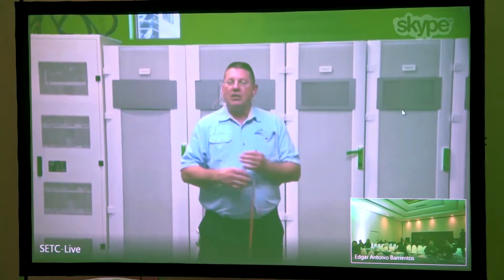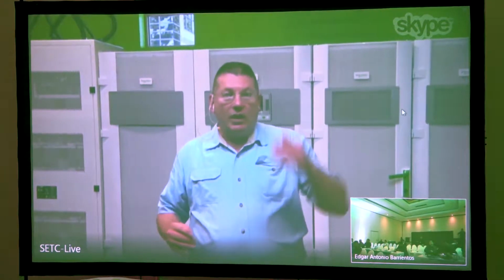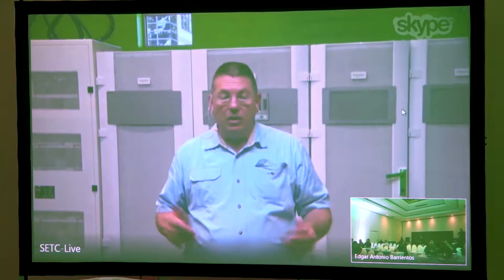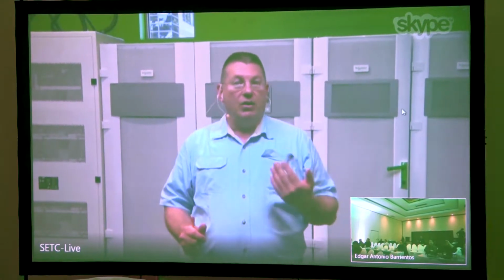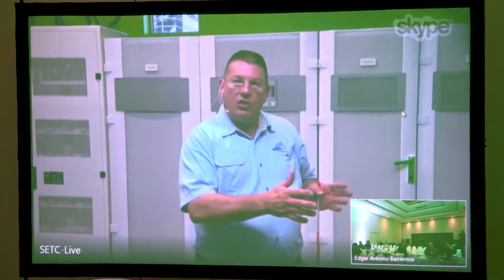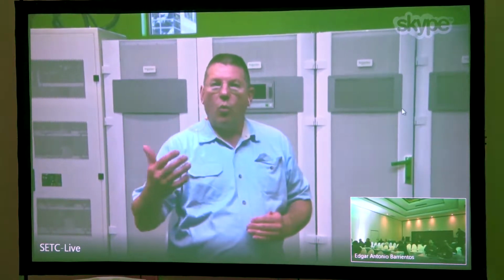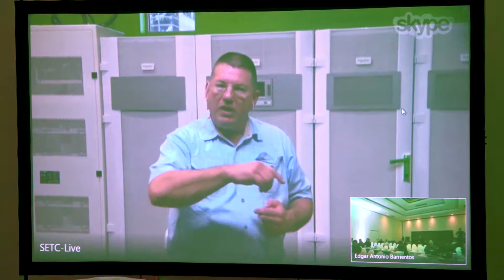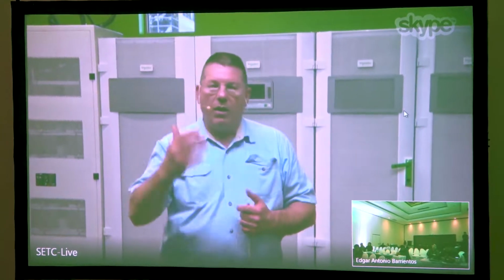So back to the GVX, 500 to 1500 kilowatts in size. The unit can do top or bottom feed, it's just a matter of an access plate into the input-output cabinet, what we call the IOC. There's no rear access requirement on this UPS, so we can push it up against the wall and save space, which translates to more white space in the building versus having to use space around the UPS for access.